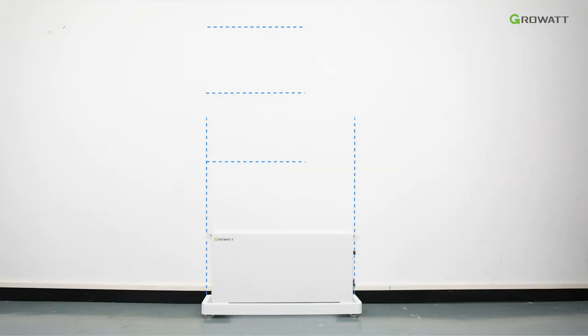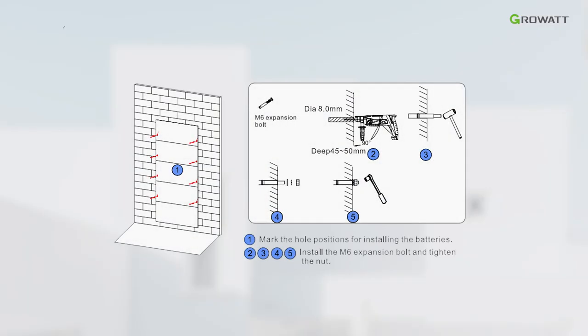Move away the second battery. Determine the hole positions for mounting the remaining batteries and mark them. Drill with an 8 mm diameter alloy bit. The hole depth 45 mm to 50 mm. Install the M6 expansion bolts.